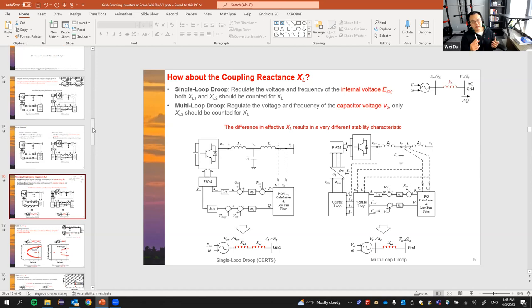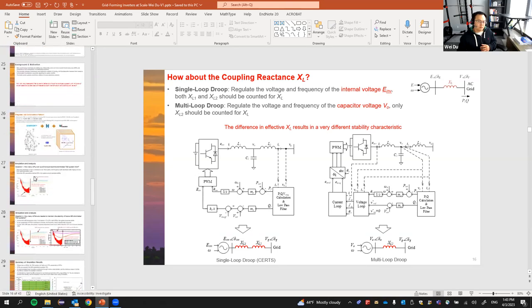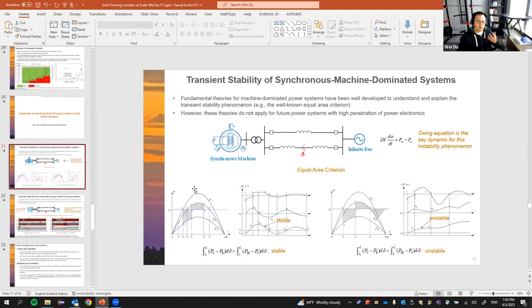We only add a 10 millisecond filter. I think that worked pretty well for harmonic loads and also for the unbalanced loads, right? You filter out those 120 Hertz oscillations. And during normal operation, I do not see the need to add inertia. I think adding inertia is potentially just going back to the synchronous machine dominated system, right? Because when you have this swing equation, these three equations cause oscillations. And for machines, this is something that you cannot avoid. But for grid forming inverters, if you bring them back, you just create some problems for yourself. So I think we don't need to have that in normal operation.